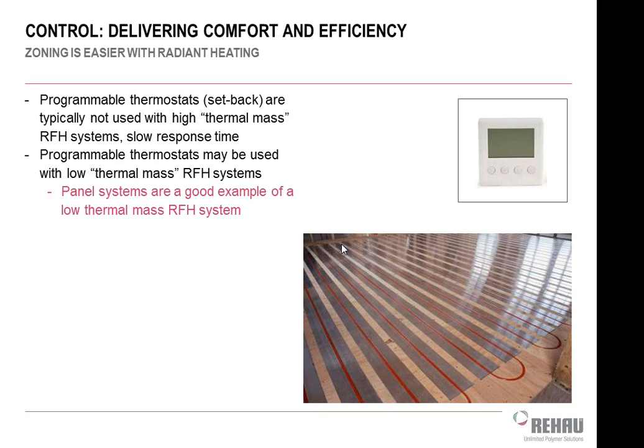So the good news about that is that once I get the floor warm, it doesn't take a lot of energy anymore. That first day, yeah, I run my boiler nonstop all day and get the floor warm. But then once it's warm, all I'm doing is maintaining the heat of that floor. I don't want to put the thermostat into a setback mode, because if it goes into setback mode and says I don't want 70 degrees in the space anymore, I want 65 degrees in the space, it's going to take me 3-4 hours with that floor being off to cool the air in that space down.